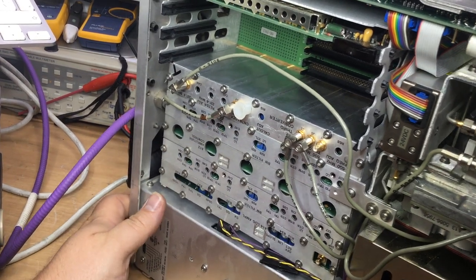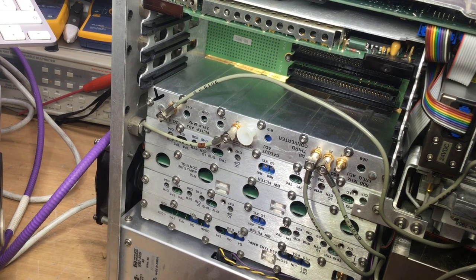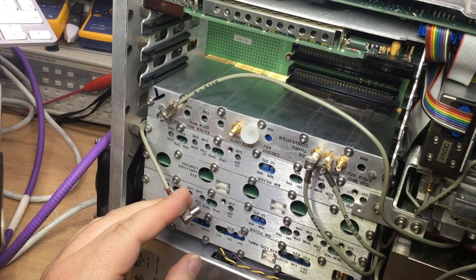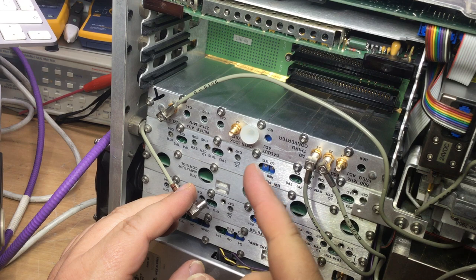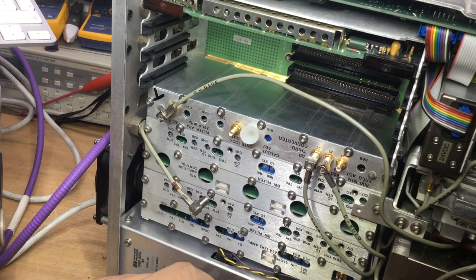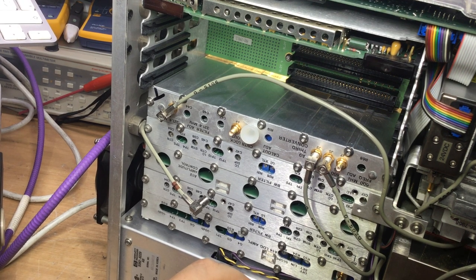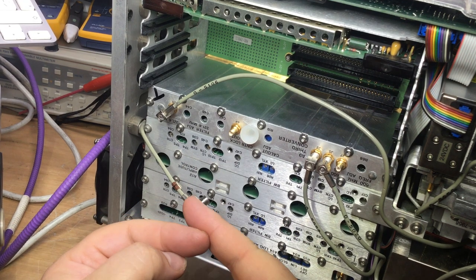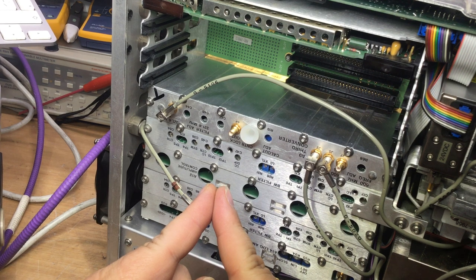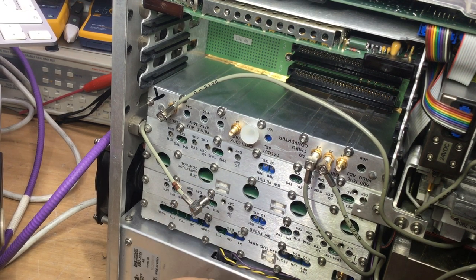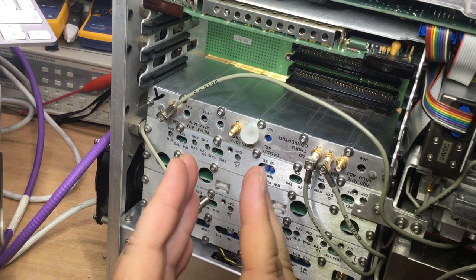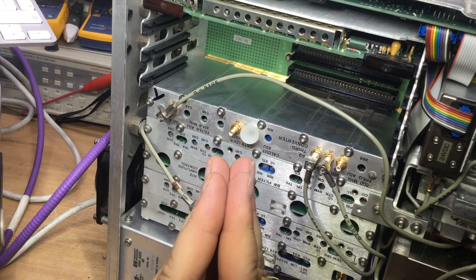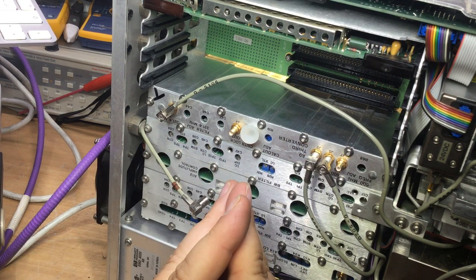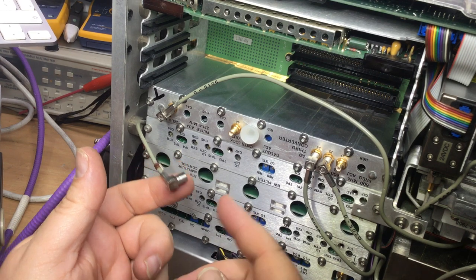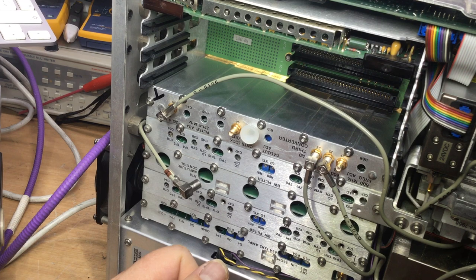Right, J3's here. What we need to do is intercept that now, because naturally, once we unplug that from here, we'll disturb the oscillator, because it would lose the signal, assuming it's there, going to the phase lock loop, which is on another part of the system we were looking at earlier on the diagram, where it compares the 10 meg input as well as what comes out of here, which should be the 600 megahertz, and then the difference would be the tune volts. And the tune volts would move the varactor diode, or the oscillator, influencing its frequency to keep the 600 MHz on frequency, and thus the accuracy of the instrument would be maintained. Now, because we've unplugged this, potentially that loop, if it is in lock, goes out of lock, and therefore it can mess our measurement up.